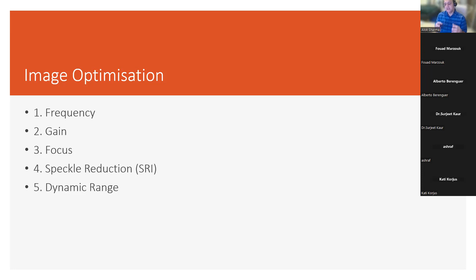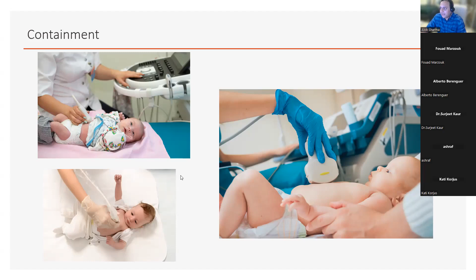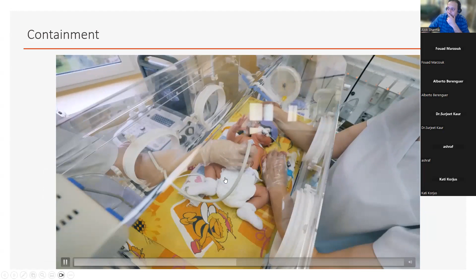Now, really, we've talked in the last class about containment, and containment is crucial. And the reason I'm emphasizing this again is because your images and the quality of your images, you can play with the machine as much as you want, but if you've got a baby that's moving all around, or you're trying to image the lower part of the lateral region with clothes, you're just not going to get good images because you're not going to get good contact. And if you do not have good contact, altering the actual machine is not going to make any difference at all. So it is absolutely crucial that you consider and alter images only if you're absolutely certain that you have got a baby that you can control.